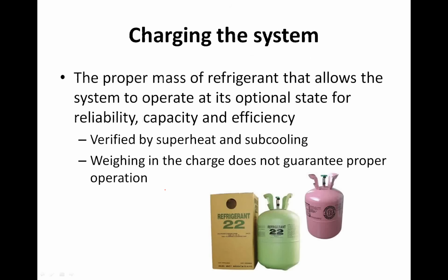So let's talk about that. When talking about charge, we're talking about the proper mass of refrigerant that allows the system to operate at its optimal state for reliability, capacity, and efficiency. That means there's pretty much only one correct charge. You've got to nail the numbers. We verify it's correct by superheat and subcooling. And weighing in the charge does not guarantee proper operation, right?